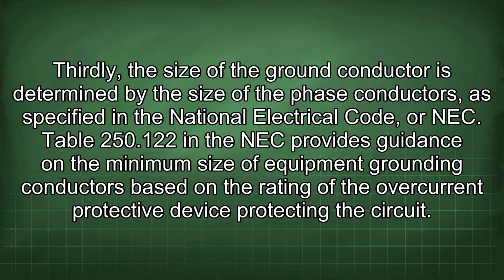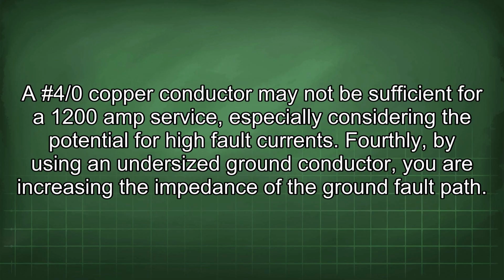Table 250.122 in the NEC provides guidance on the minimum size of equipment grounding conductors based on the rating of the overcurrent protective device protecting the circuit. A #4/0 copper conductor may not be sufficient for a 1200 amp service, especially considering the potential for high fault currents. Fourthly, by using an undersized ground conductor, you are increasing the impedance of the ground fault path.